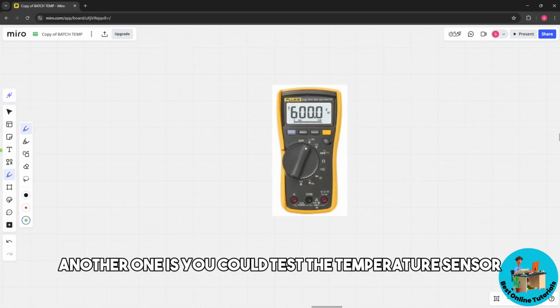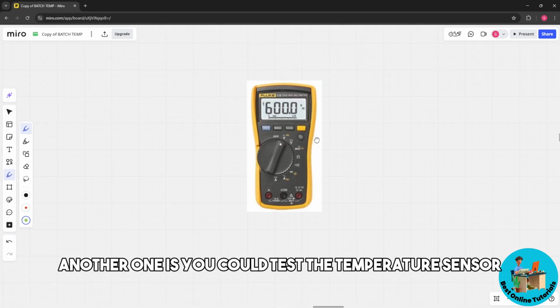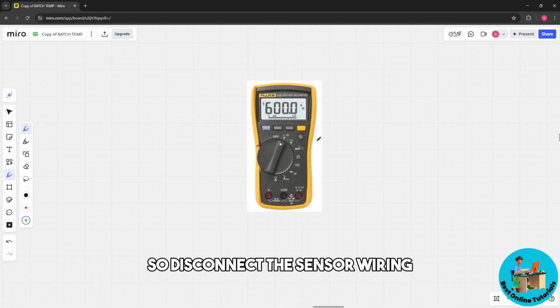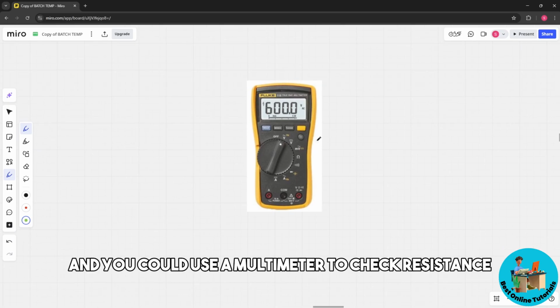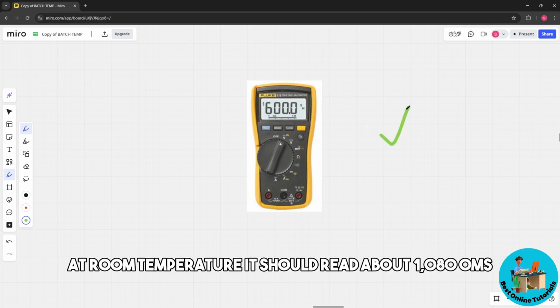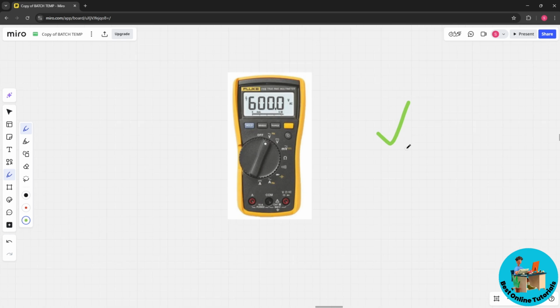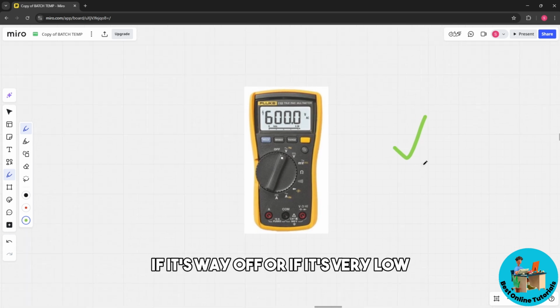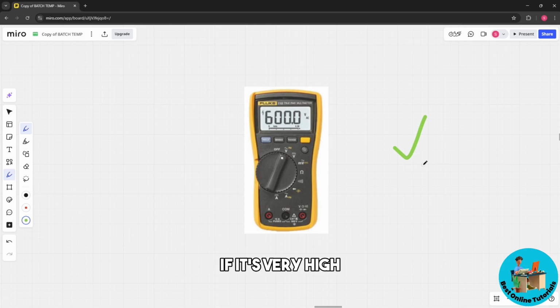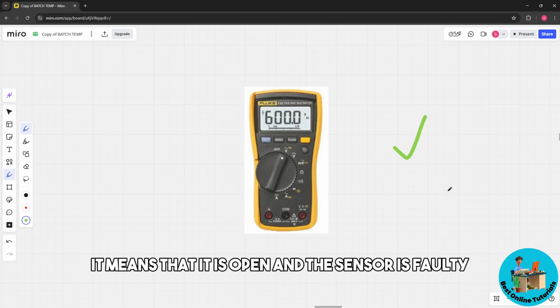Another option is to test the temperature sensor. Disconnect the sensor wiring and use a multimeter to check resistance. At room temperature, it should read about 1080 ohms. If it's way off or very low, it means it is shorted. If it's very high, it means it is open and the sensor is faulty.